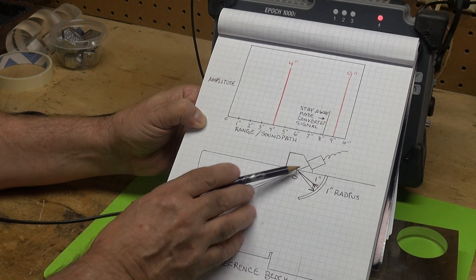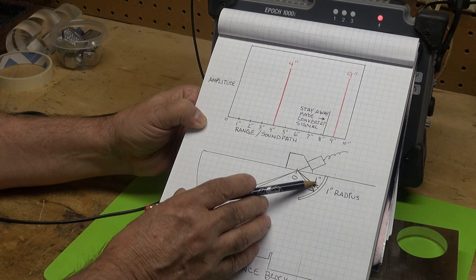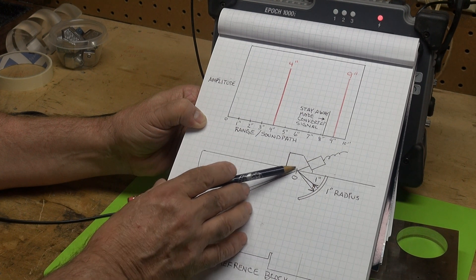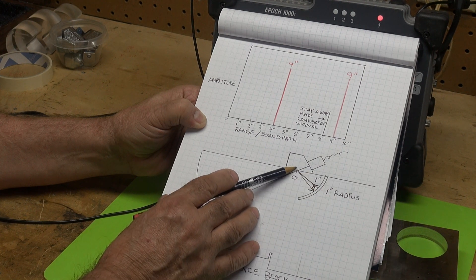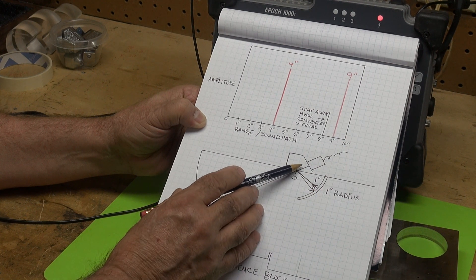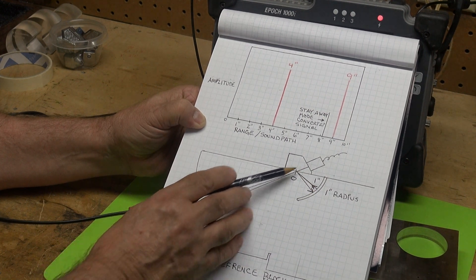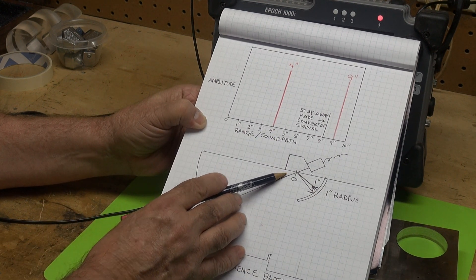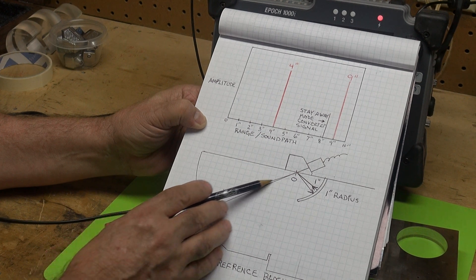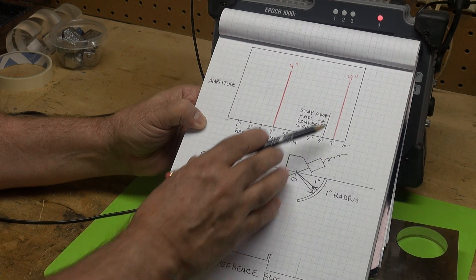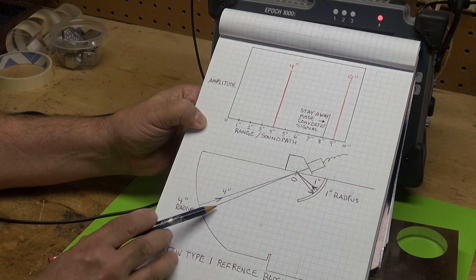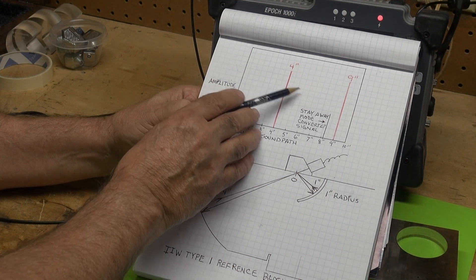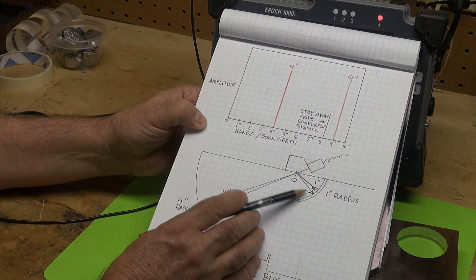That 1 inch radius will come back, so we have 4 inches plus 1 inch. But that 1 inch when it comes back does not strike the transducer at a perpendicular angle, so we won't see it. We see 4 inches, and then 1 inch is 5, and then 4 more inches coming back will be 9 inches. So it's 4 plus 5 is 9.